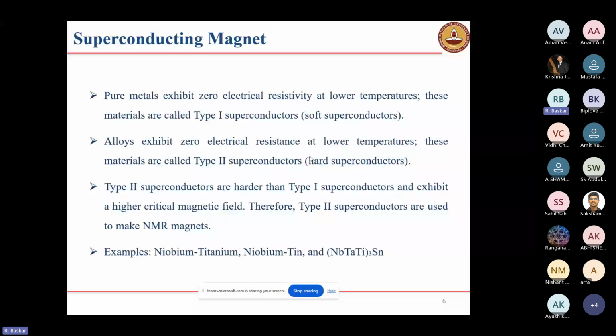In general, for NMR purposes, type 2 superconductors are used because they have a lot of thermal stability and mechanical stability also. Niobium titanium and niobium tantalum titanium tin alloys are used. Up to 12 Tesla, generally people are using niobium titanium alloy, so it has more mechanical stability, but it will generate a maximum of 12 Tesla. Above 12 Tesla, people are using niobium tin alloy, so it has lower mechanical stability.